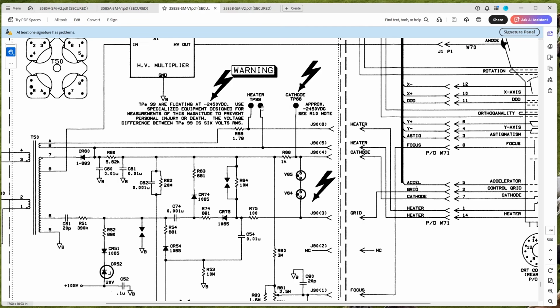But what we can do is just probe that and at least we'll see if we're getting voltage on that. So let's go do that. Let's put it on just one of those test points. There we go. And let's turn the unit on again. And there we go. We can see that it's 2461 there, and it's showing that at least we're getting something at the correct level. 2461 there, 62, plus or minus 1%. Anyway, I think we're probably okay with getting heater voltage out of there.